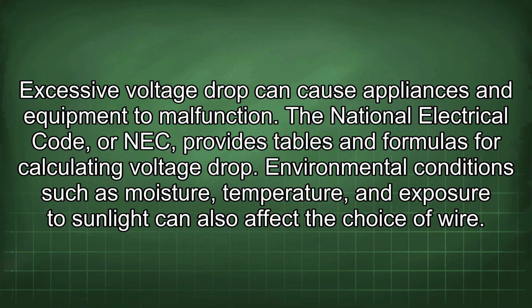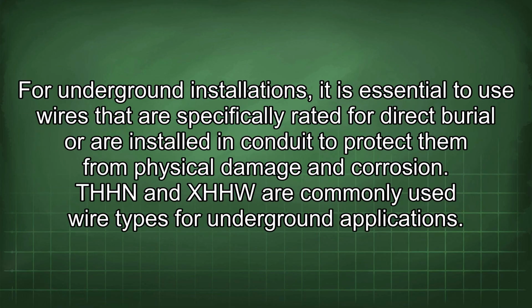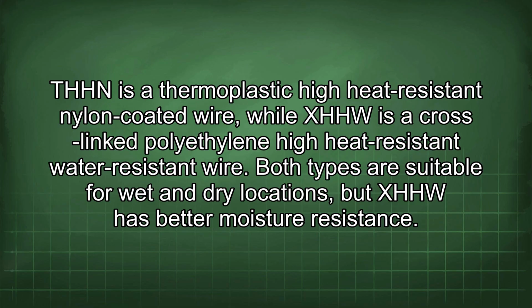The National Electrical Code, or NEC, provides tables and formulas for calculating voltage drop. Environmental conditions such as moisture, temperature, and exposure to sunlight can also affect the choice of wire. For underground installations, it is essential to use wires that are specifically rated for direct burial or are installed in conduit to protect them from physical damage and corrosion. THHN and XHHW are commonly used wire types for underground applications. THHN is a thermoplastic high heat resistant nylon coated wire, while XHHW is a cross-linked polyethylene high heat resistant water resistant wire. Both types are suitable for wet and dry locations, but XHHW has better moisture resistance.